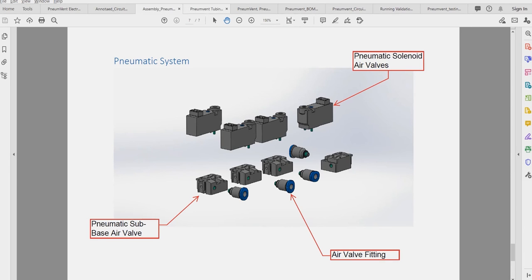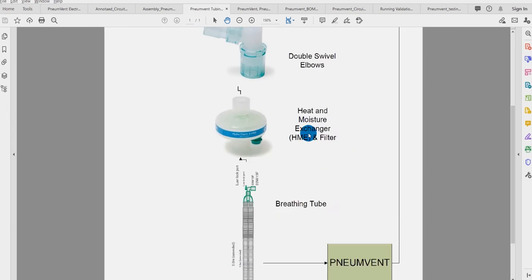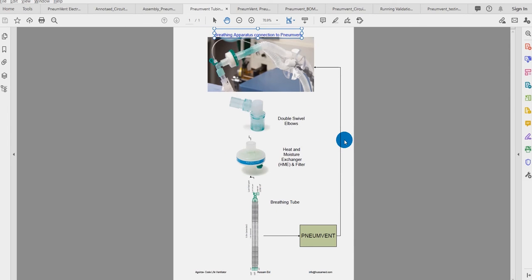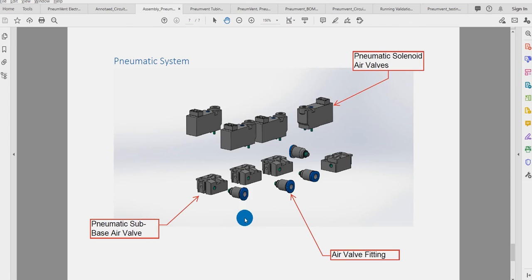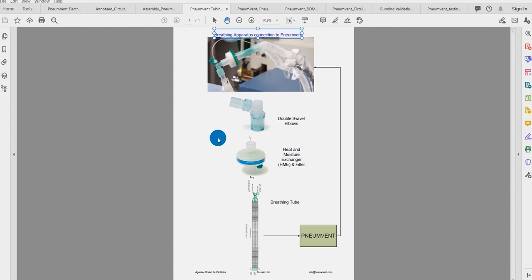Now, if we take a look at the assembly system from outside, so how a nurse or technician is going to hook up the system, we are using a breathing tube with two tubes, one for inspiration, one for expiration, connected from this end to the pneumatic system I showed earlier, using an adapter. So it connects there. And finally, secondly, we connect it to a heat and moisture exchanger and filter, and then it connects to a double swivel elbow.